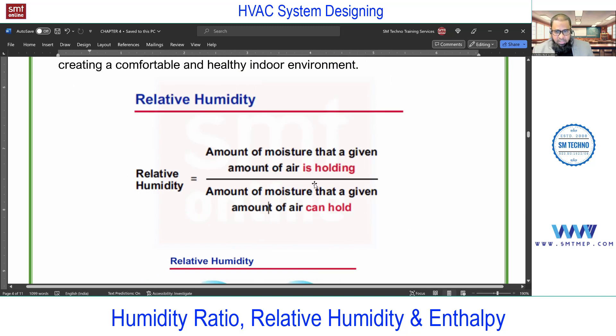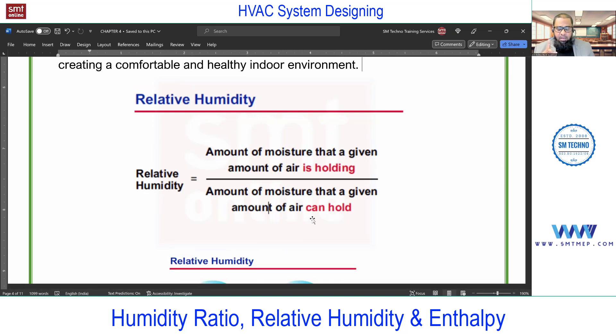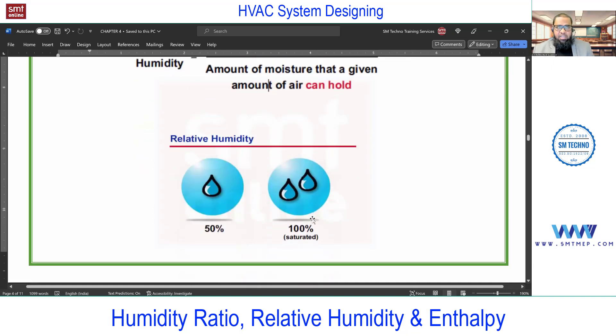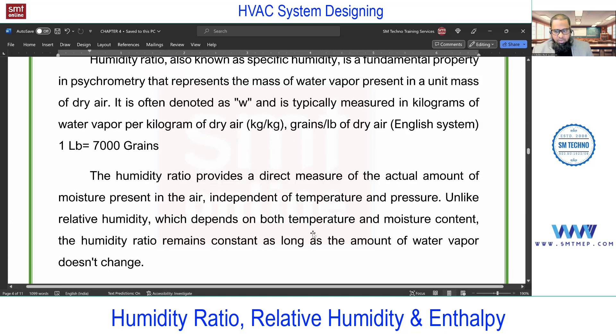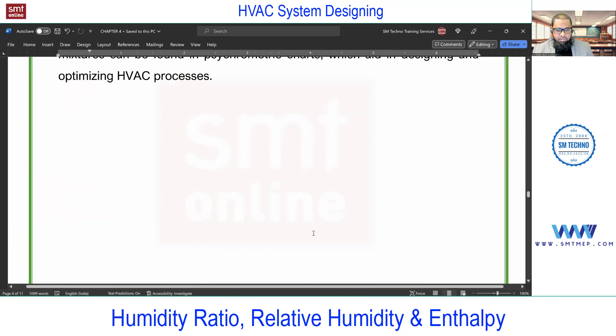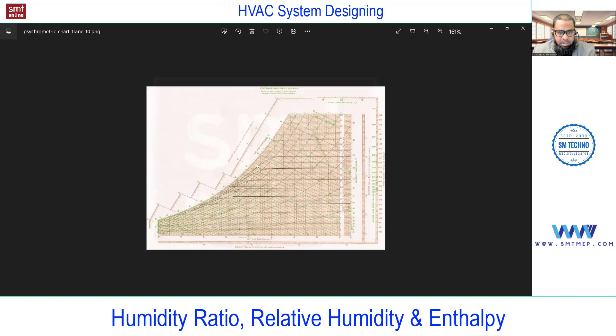To summarize relative humidity: it is the ratio of the amount of moisture a given amount of air is holding to the amount the air can hold at saturation condition. An important point to note: when the air is saturated, the dry-bulb temperature, wet-bulb temperature, and dew-point temperature are all equal. This is worth noting for interview purposes.